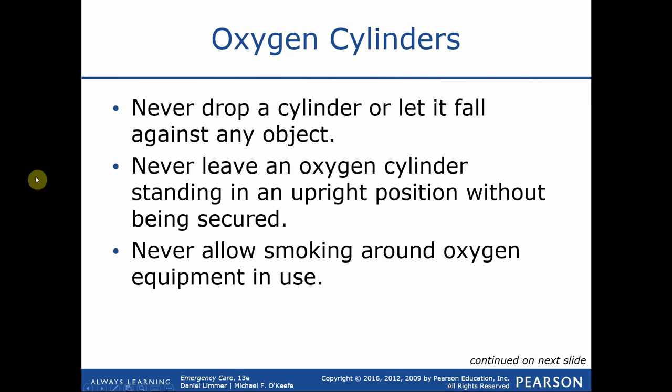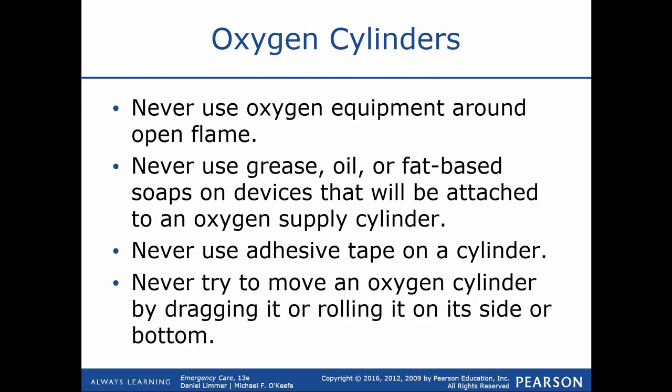Never drop a cylinder or let it fall against any object. Cylinders stored upright must be secured in a rack or chain. If a tank falls and the neck fractures under high pressure, it can become a projectile — there are documented cases of tanks flying through walls. If a tank cannot be secured upright, lay it flat and ensure it cannot roll. Never use oxygen around open flames.